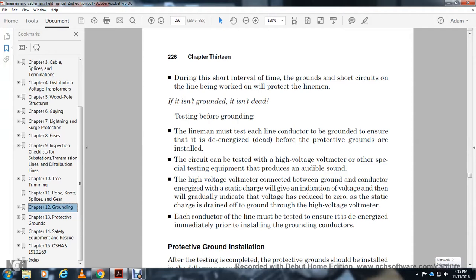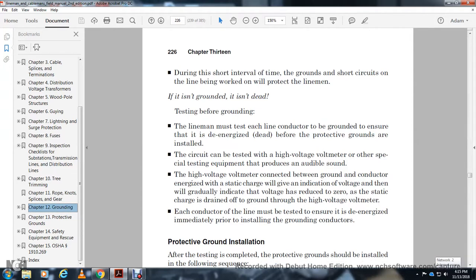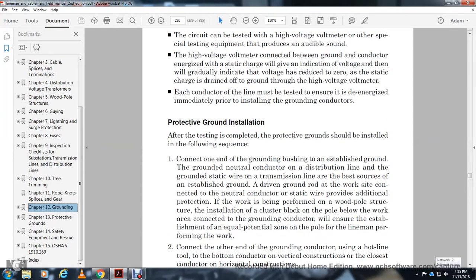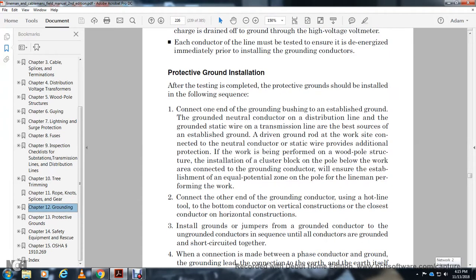As the static charge is drained off to ground through the high voltage voltmeter, each conductor of the line must be tested to ensure that it is de-energized immediately prior to installing the ground conductors. Protective Ground Installation. After testing, the completed protective ground should be installed in the following sequence.